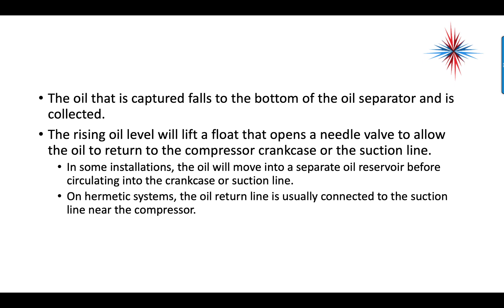The oil that is captured falls to the bottom of the oil separator and is collected. The rising oil level will lift a float — similar to a toilet tank float — that opens a needle valve to allow the oil to return to the compressor crankcase or the suction line. In some installations, the oil will move into a separate oil reservoir before circulating in the crankcase or suction line.